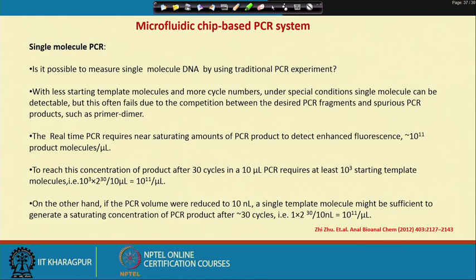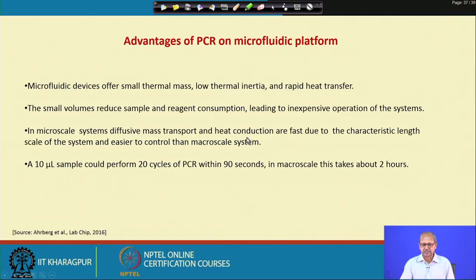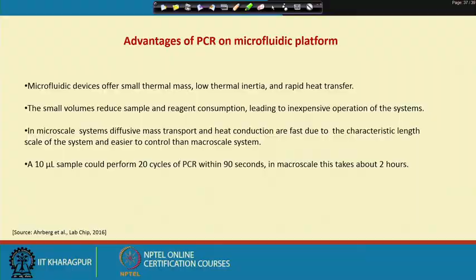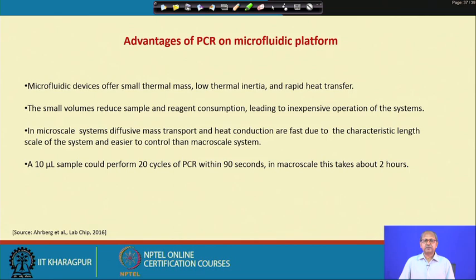What are the advantages of microfluidic PCR? Microfluidic devices offer small thermal mass, low thermal inertia, and rapid heat transfer. Small volumes reduce sample and reagent consumption, leading to inexpensive operation. At the microscale, diffusive mass transport and heat conduction are fast due to the short characteristic length scale. A 10-microlitre sample can perform 20 cycles of PCR within 90 seconds, whereas normally it takes around 2 hours — the time can be reduced to as little as 60 seconds.